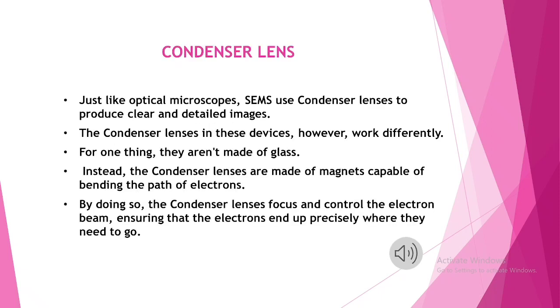The next component is the condenser lens. As the name suggests, its main role is to control the size of the beam. For a given objective aperture, the beam size determines the number of electrons in the beam which hit the sample. Up to three condenser lenses are often used in SEMs. The greater the lens strength, the smaller the resulting beam diameter and the greater the convergence angle. In electron microscopes, electromagnetic lenses are used.